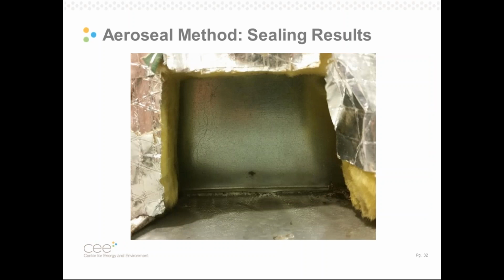And here's another result. This one is kind of goofy. It might be a little bit hard to see, but this is a branch takeoff off the top of a supply plenum, and there's actually a huge gap. Find my cursor. Huge gap running horizontally between the takeoff and the supply plenum. It's about a 1/4 inch thick, and it runs at least this entire section, but probably all around the perimeter of this ductwork. This picture was actually taken halfway through the sealing process. So we can see on the left, the accumulation of that white sealant has filled some of the gap, and on the right, it's still actively sealing that gap.